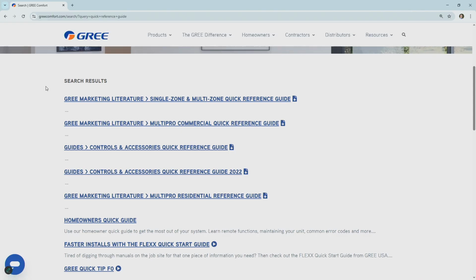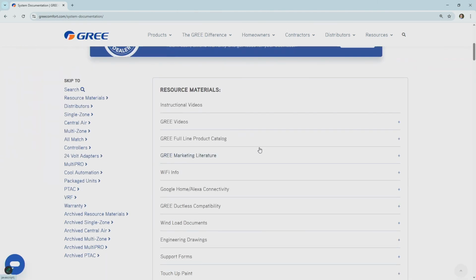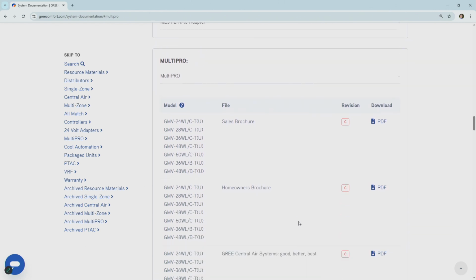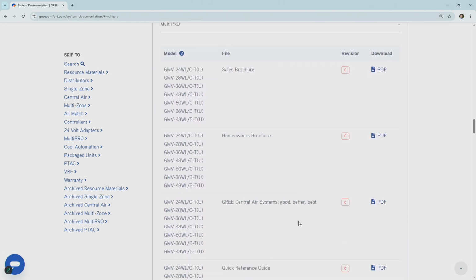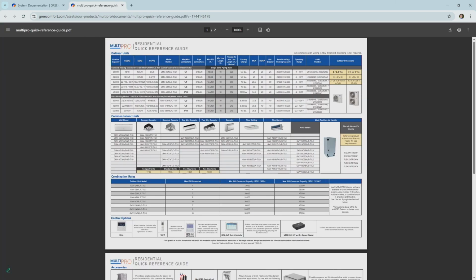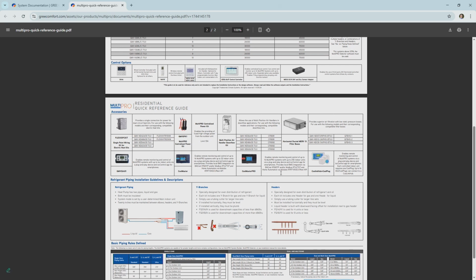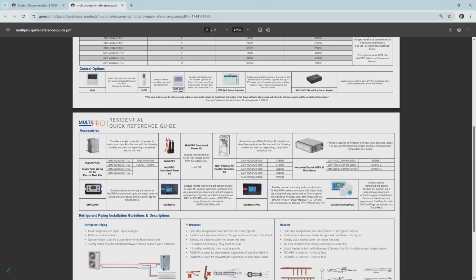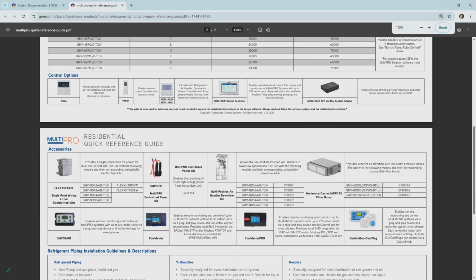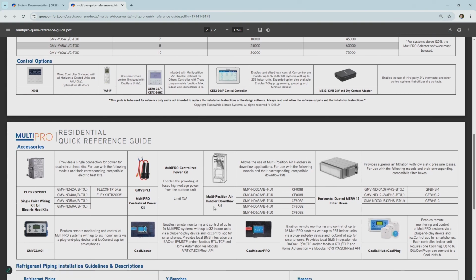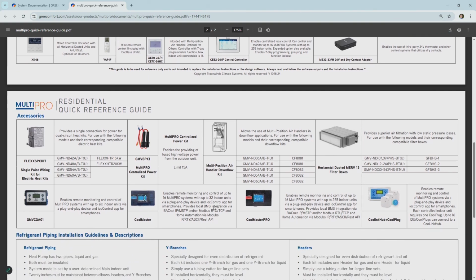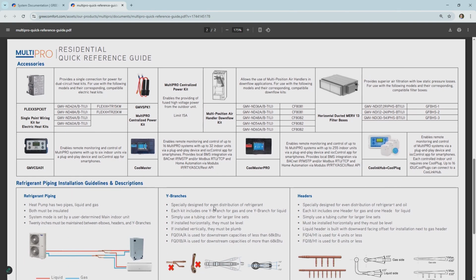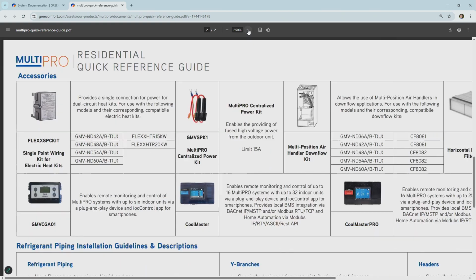So go under resources, system documentation, go under MultiPRO, right there. Quick reference guide right there. All right, we scroll down just a little bit. There it is right there, MultiPRO centralized power kit. What that's for, again, is if you need to power the indoor units. Like I said, if you're taking out a multi-zone unit, you already have 14/4 wire run to those indoor units. You can use 3 of those wires as your power source to the indoor unit coming off of the outdoor unit. So essentially you're going to have your L1, your L2, and a ground. That's 3 of your wires. The 4th wire you won't use.